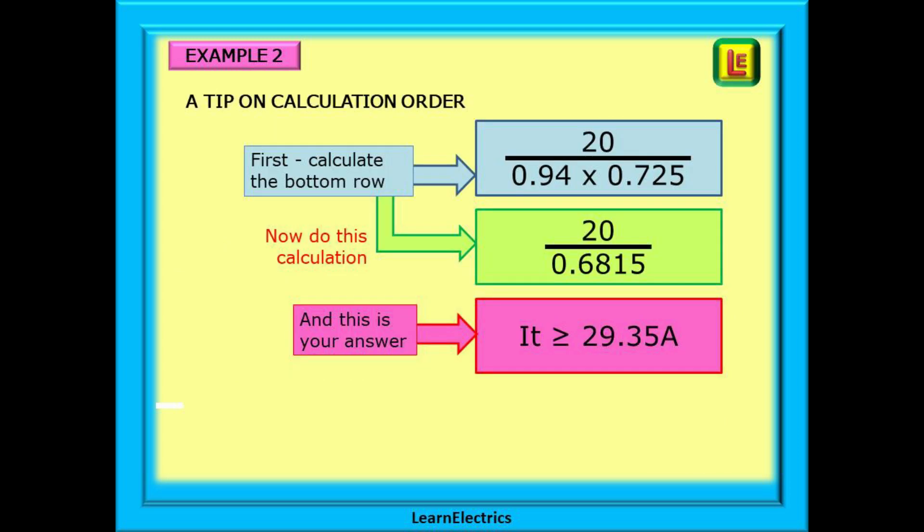A tip on calculation order. It is so important that you get this calculation right. Here is one method. First, calculate the bottom row and write the answer down. 0.94 multiplied by 0.725 is 0.6815. Now do the calculation. 20 divided by 0.6815 and this is your answer. It must be equal to or greater than 29.35 amps. If you get something like 14.5 amps you've gone wrong. Follow this method and you will get the right answers.